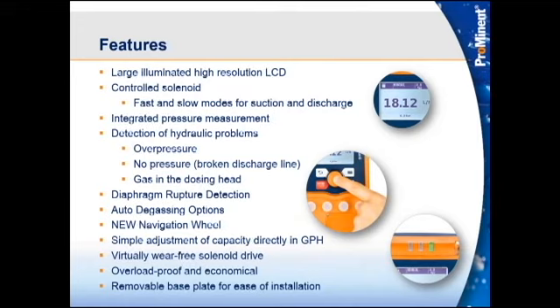I no longer can see, the pump won't even let me see what the stroke length is or what the frequency is. When Germany developed this pump, they knew what the appropriate dosing profile looks like. So based on that pump model and the capacity you enter, it's going to be able to meet and give you the best possible dosing profile for that. Okay, and depending on hydraulic changes and different changes in the system, the pump is always adjusting that stroke length and frequency. So it doesn't let you see any of that. Also, in automatic mode, it will compensate if the pressure changes or varies a little bit. It will adjust the frequency to meet that.